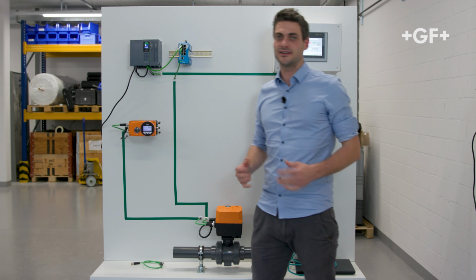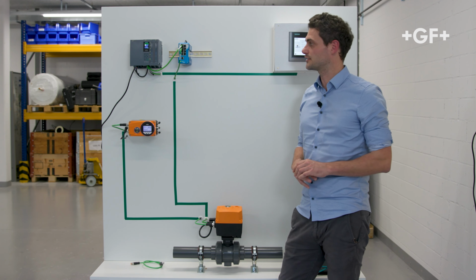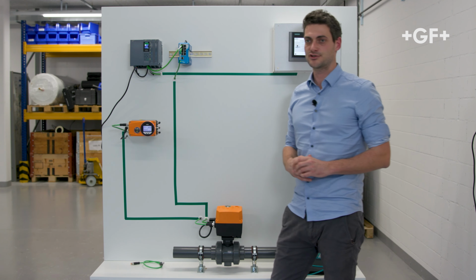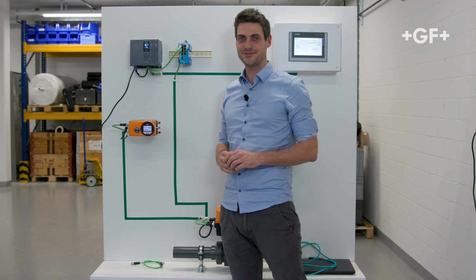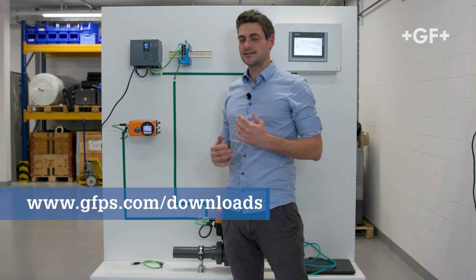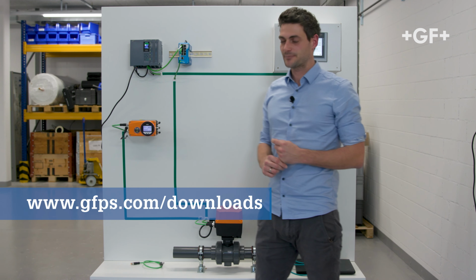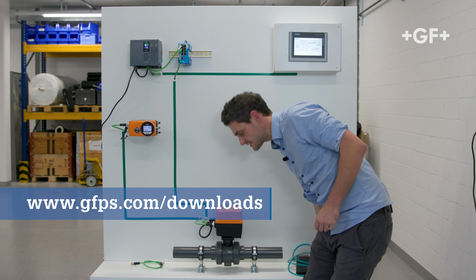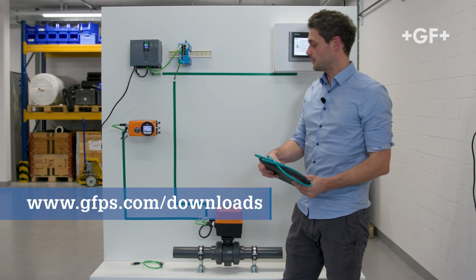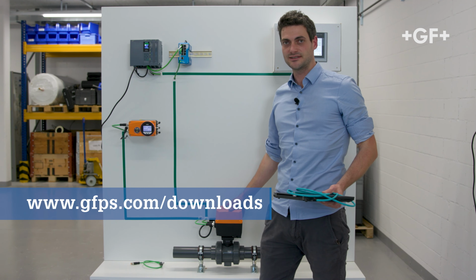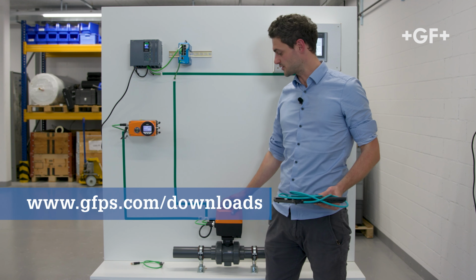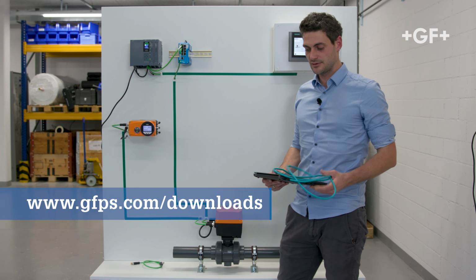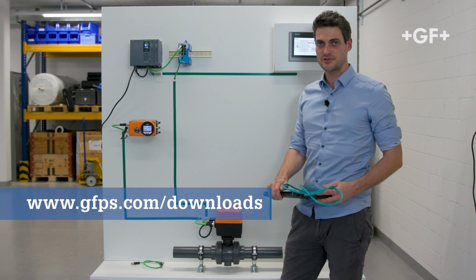In terms of Profinet, this device driver is called GSD, which stands for General Station Description. You can download this GSD file via the GF website, but it's also possible to access this device driver directly from our electric actuator, because the device driver is stored here. So let's take a look at how easy it is to access the web server itself.